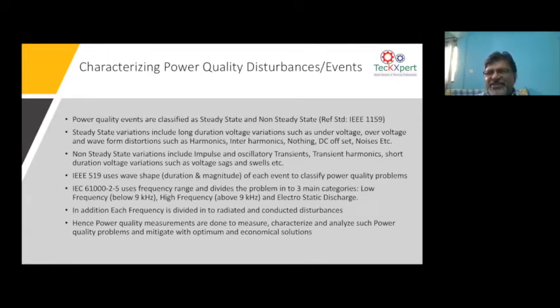first you start with characterizing the problem. That is how we can start with understanding power quality. When I say characterizing, there are standards. There are IEEE standards, there are IEC standards, which tell you how to characterize a power quality problem. When you look into power quality, the first standard that will come into focus is IEEE 1159. In 1159, power quality is classified as steady state and non-steady state. A steady state power quality problem has to do with under voltage, over voltage, or the waveform distortions like harmonics, notching, DC offset, and the noise signals that run over the power signal. We have 50 cycle waveforms. Those are all steady state wave variations.